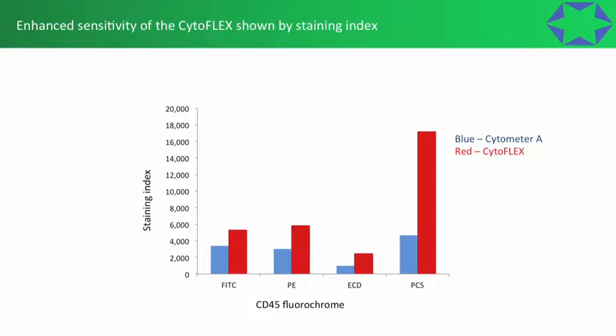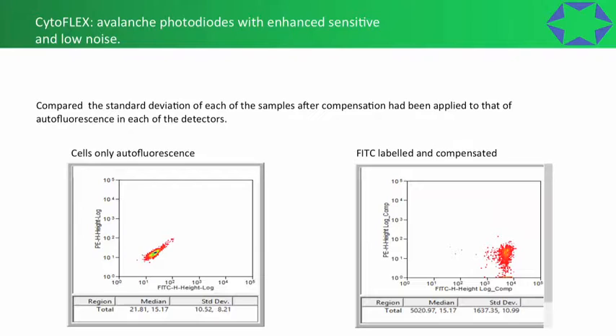To look at data spread, I took CD45 single-color on FITC, PE, ECD, and PC5, washed and fixed the cells, then compensated for all other fluorescent detectors on the 488 laser line. The staining index again echoed what we'd found previously — the CytoFLEX had a better staining index compared to the other cytometer, particularly evident in the PE-Cy5 channel with a big difference between those two bars. I'll show dot plots to help make sense of the bar charts.